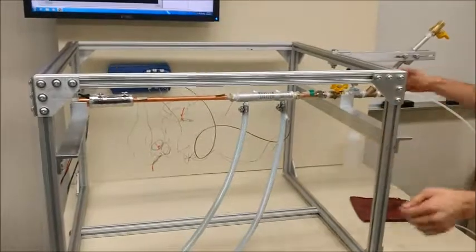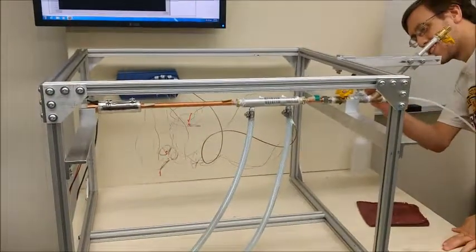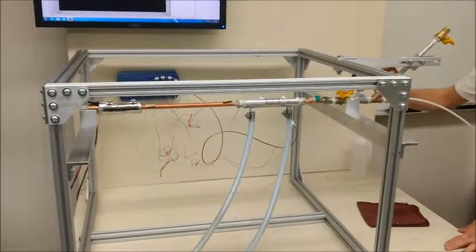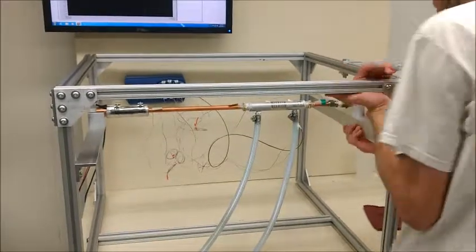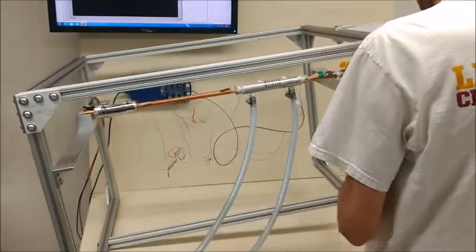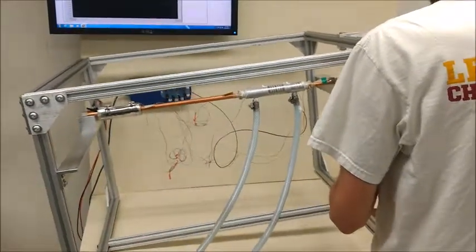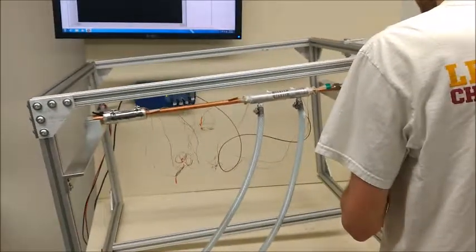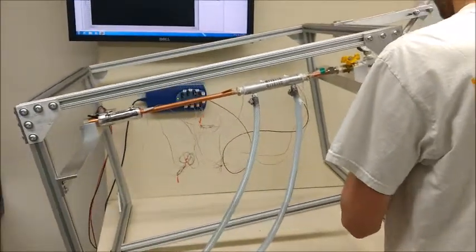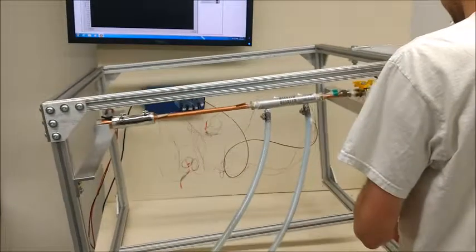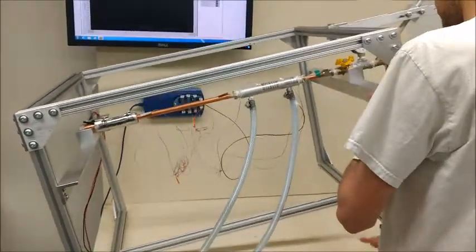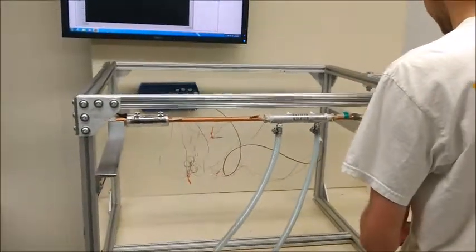We're going to do this by adding the working fluid. One thing to note is when adding the working fluid, if the pressure goes up, we know that the measuring pipe had air in it and was not full of the working fluid. Another thing to note is you can add the working fluid and then vacuum out the air by using the two bottom valves.